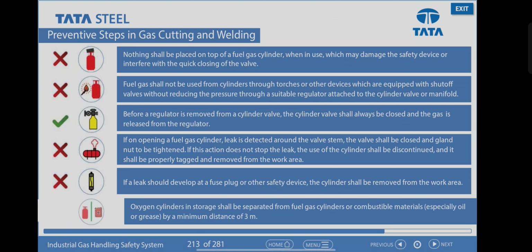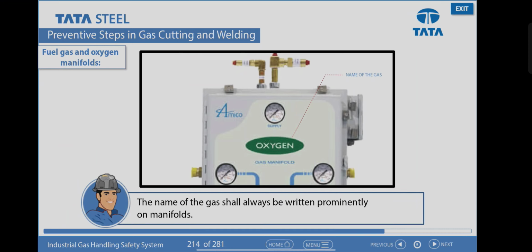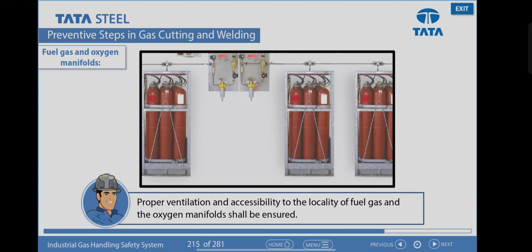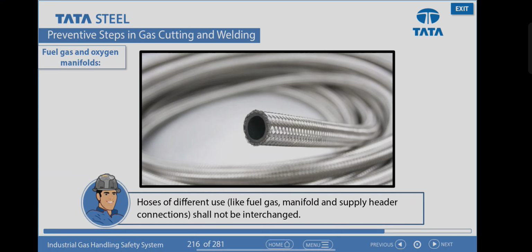Oxygen cylinders in storage shall be separated from fuel gas cylinders or combustible materials, especially oil or grease, by a minimum distance of 3.0 meter. The name of the gas shall always be written prominently on manifolds. Proper ventilation and accessibility to the locality of fuel gas and the oxygen manifolds shall be ensured. Hoses of different use, like fuel gas, manifold and supply header connections, shall not be interchanged.